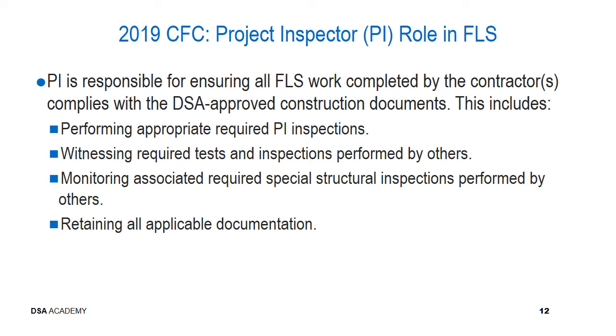So, what is the project inspector's role in FLS? Well, the PI is responsible for ensuring that all of the FLS work completed by the contractors complies with the approved documents. This includes performing the appropriate required project inspection and project inspector inspections, witnessing the required tests and inspections performed by others, monitoring the associated required fire and special structural inspections performed by others, and retaining all applicable documentation.